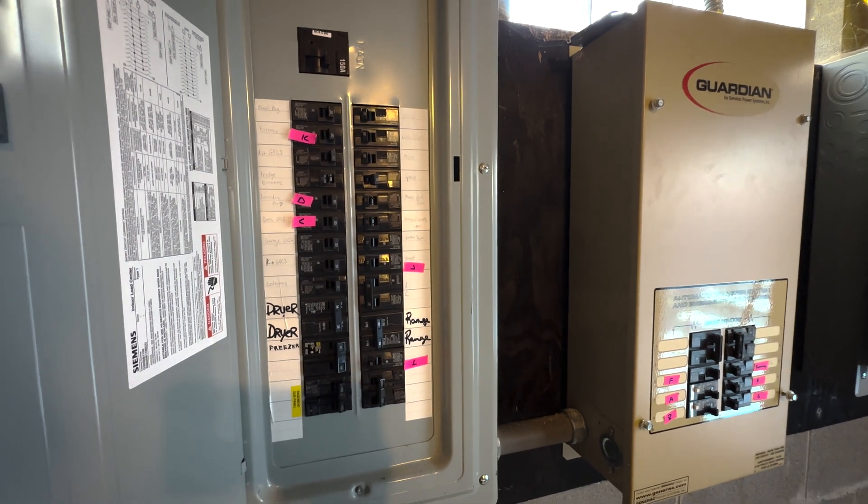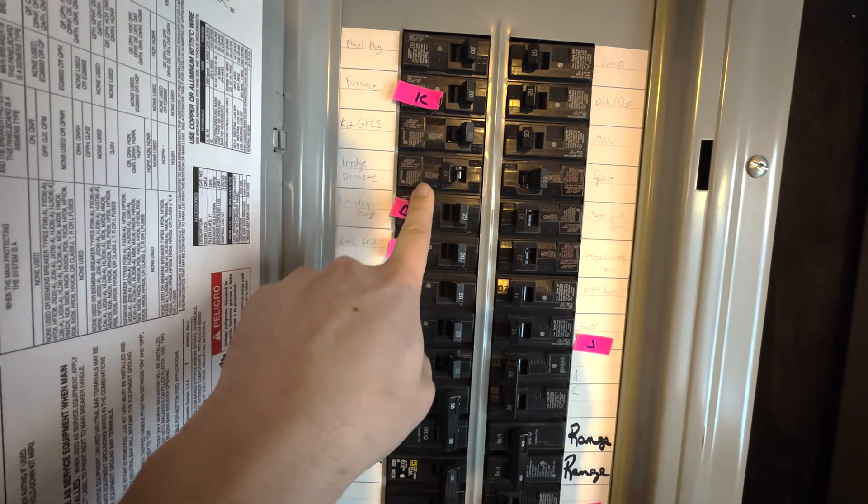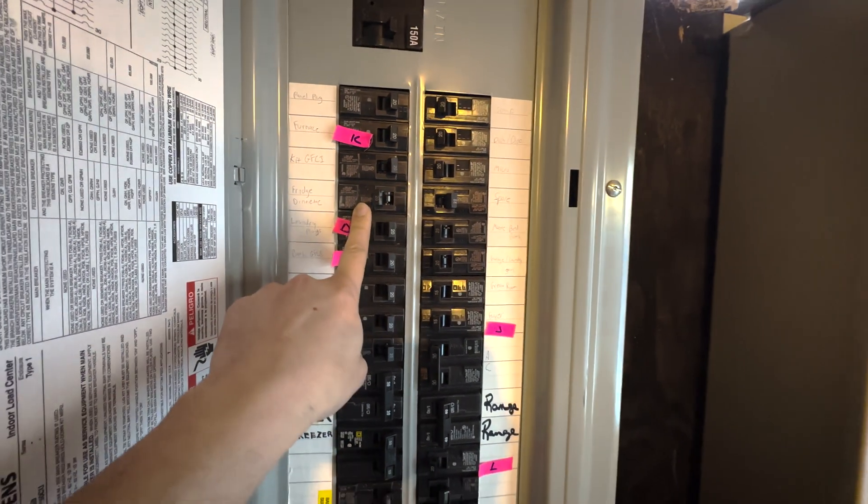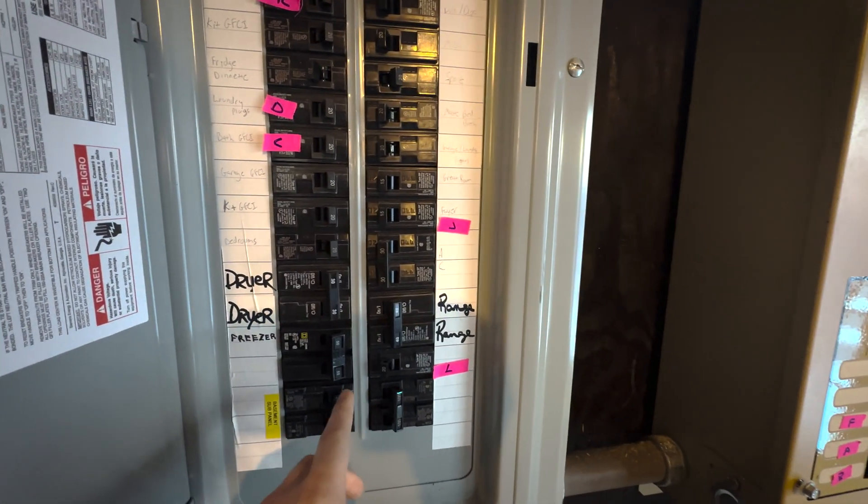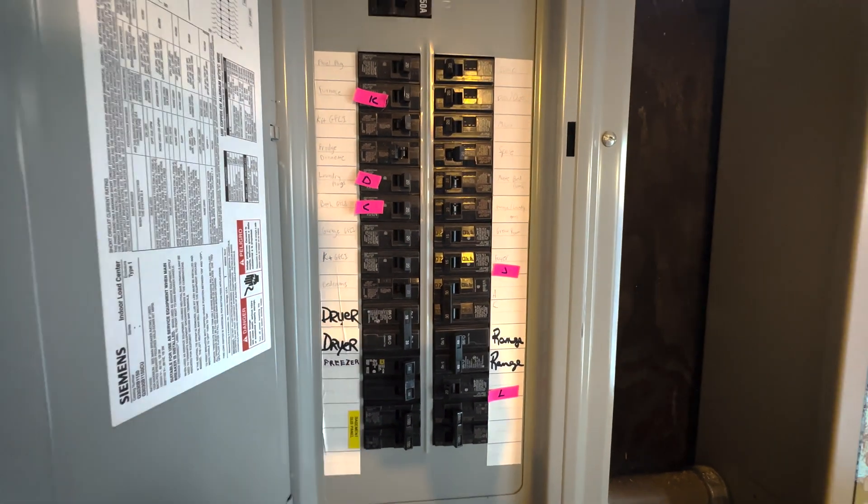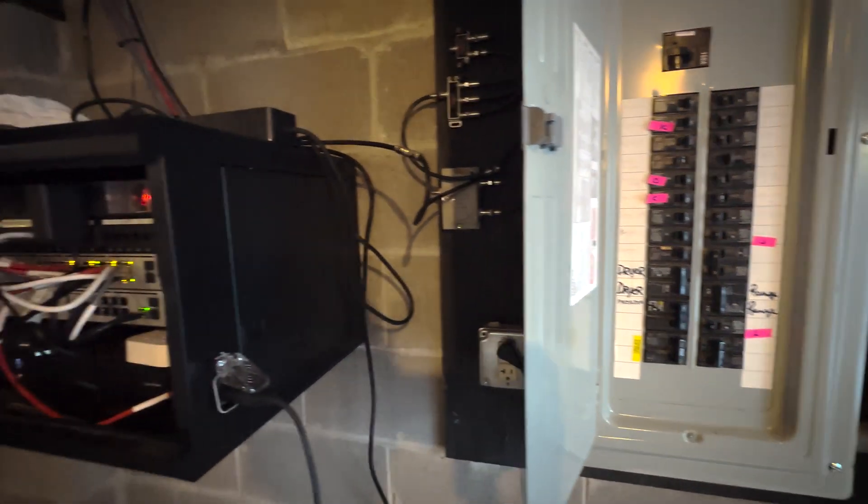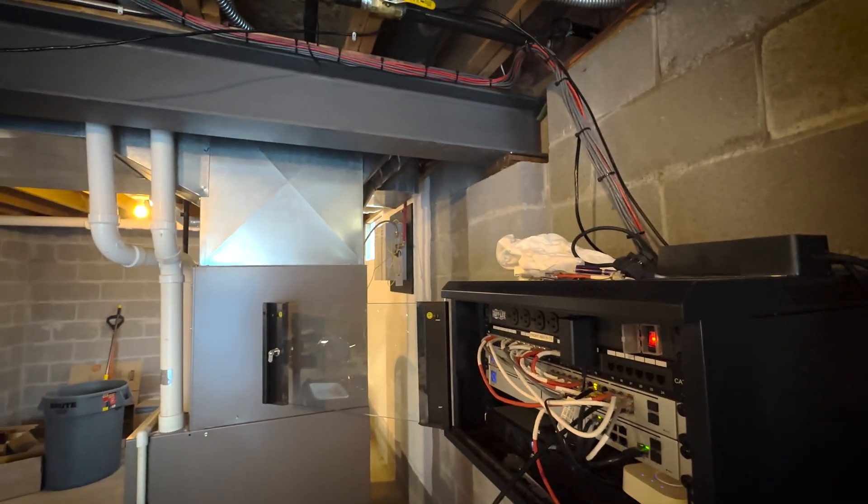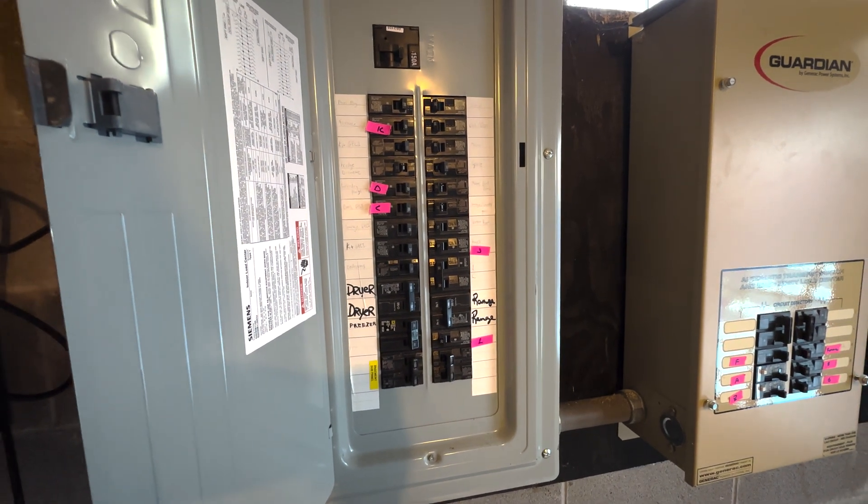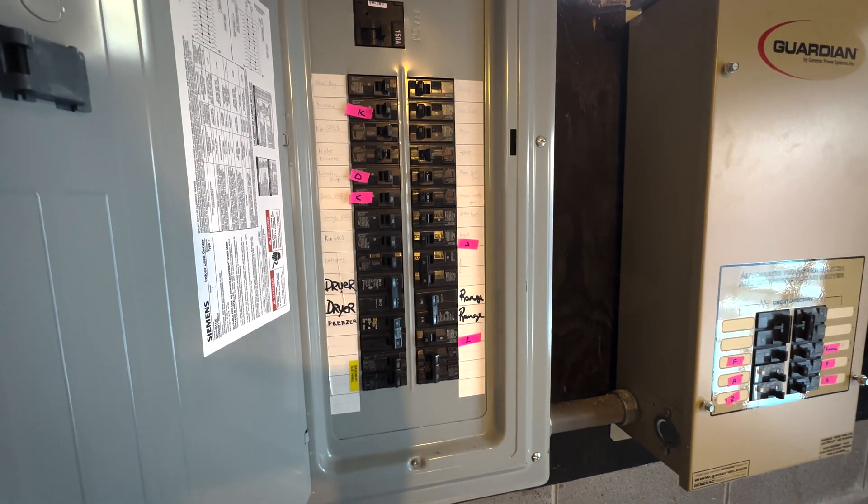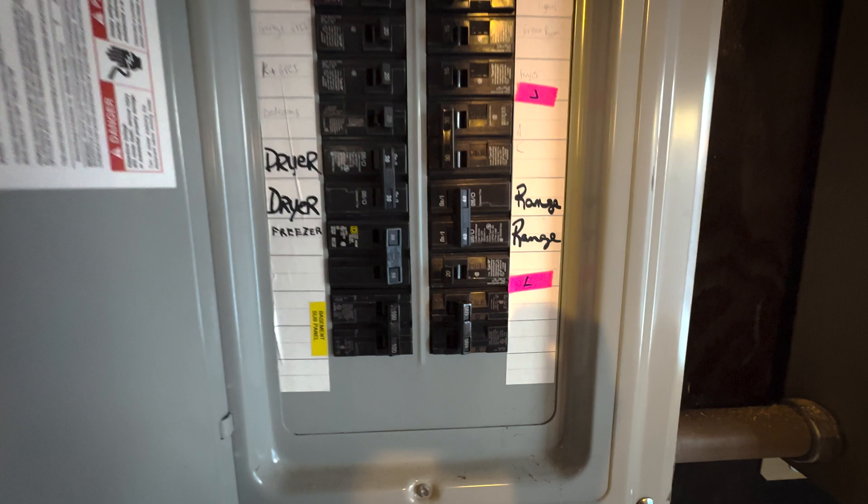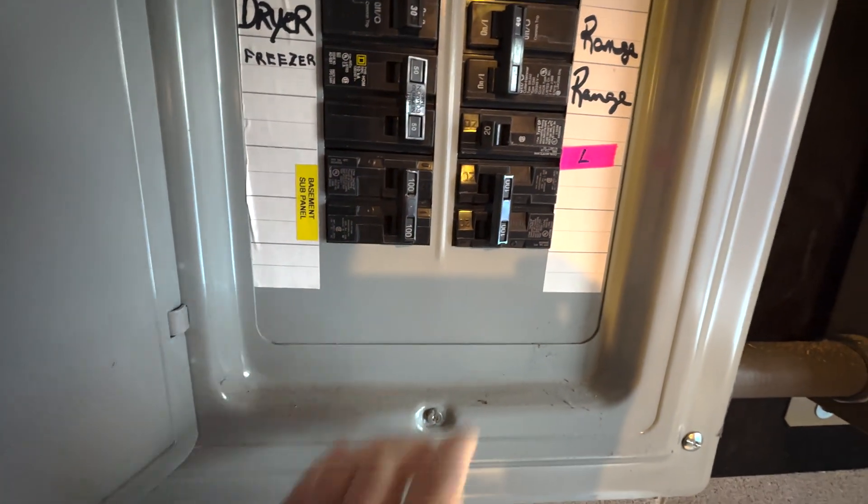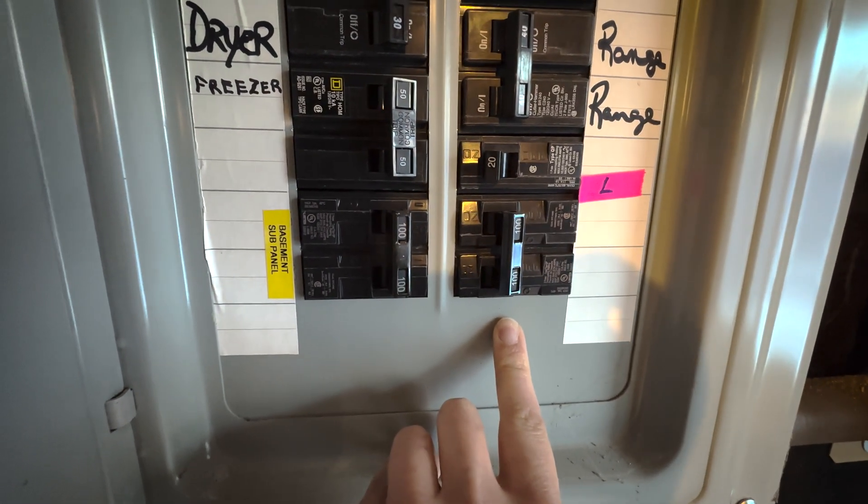So one of the projects to do today is there's a lot of these breakers that are off. And I think that they have been moved to the sub-panel here. So I'm on a fact-finding mission to do that. The other thing is I put a steam shower in upstairs. And one of the goals today is to wire that in, which is that little gray guy on the wall over there. So I'm going to pop the lid off of that and see. I believe it just needs two hots. I think it needs two hots and a ground. I don't think it needs a neutral. But before we run anything, I do have another double pole breaker that I can put in. So if you're looking down here, there's this double pole 100 amp breaker, which I don't really know what that is, which is interesting.